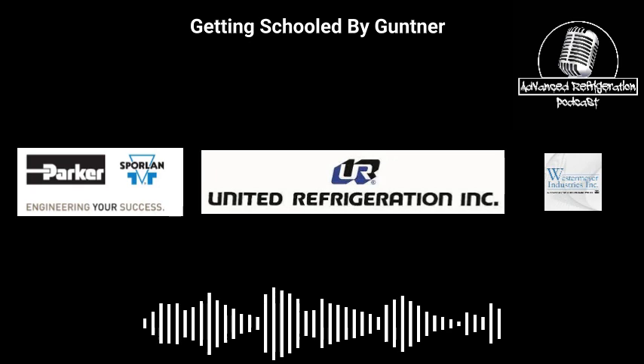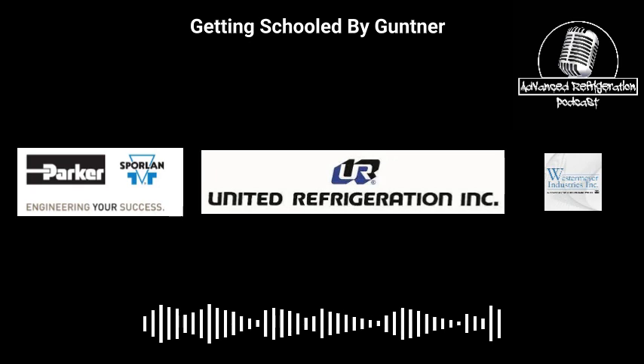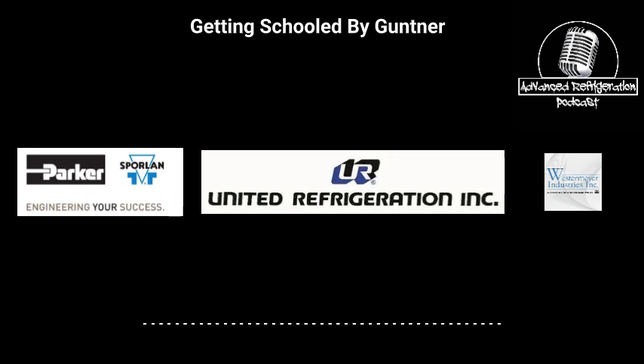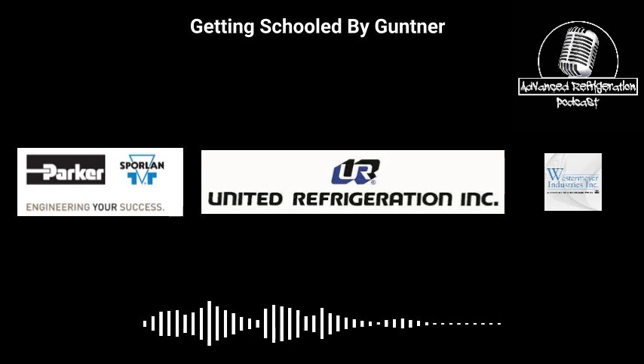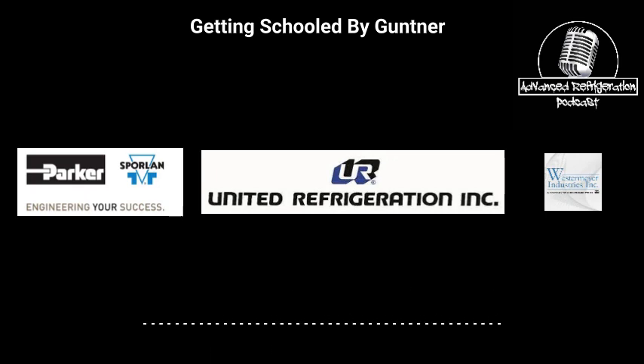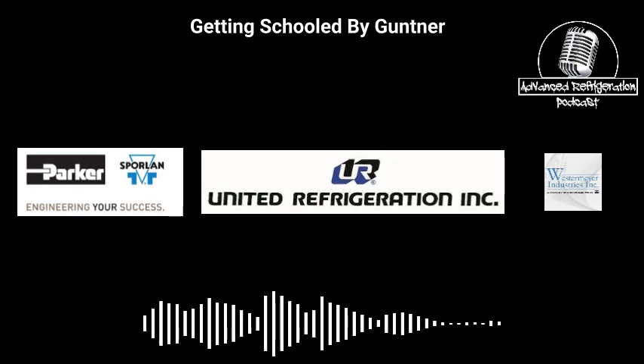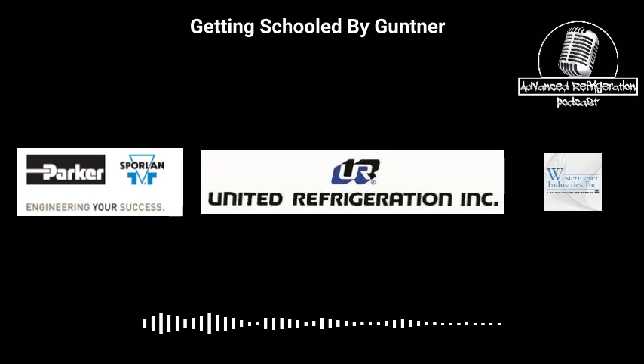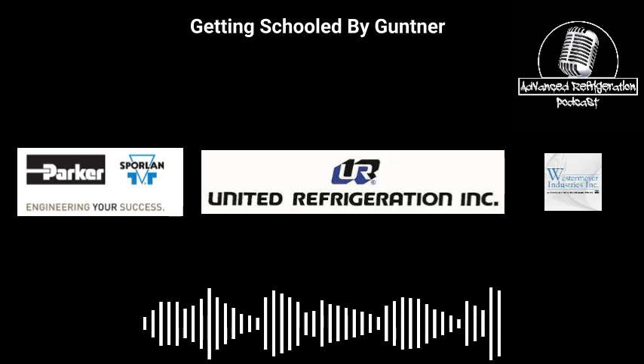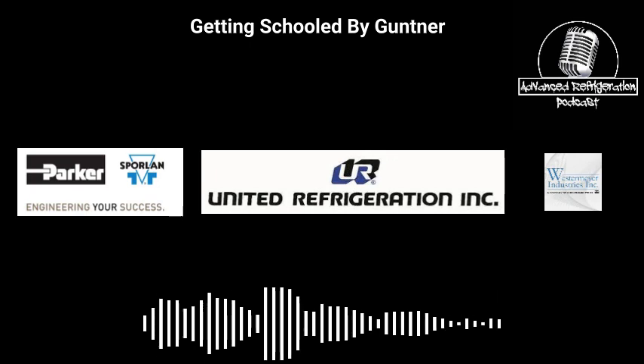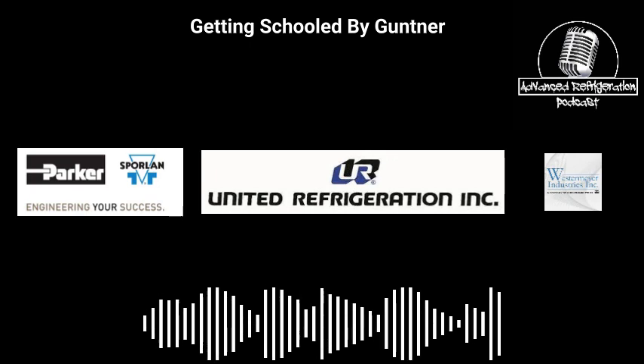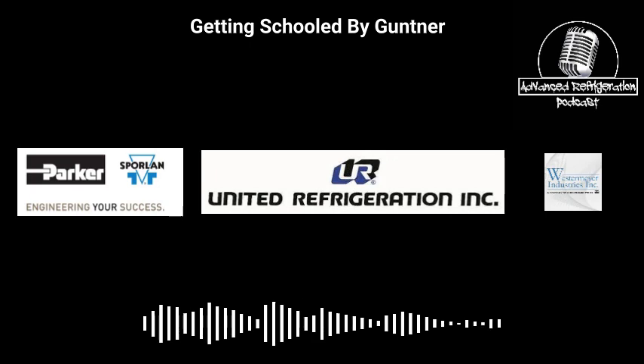So we take all those things into consideration and we put water across the pads to make them as efficient as possible. Another thing is we do record internally how much water is being used in this unit. So if we ever come across a problem where, hey, this unit's dumping a ton of water, well, let's go in there and find out exactly how much water it's used. We can do the calculations and figure that out.